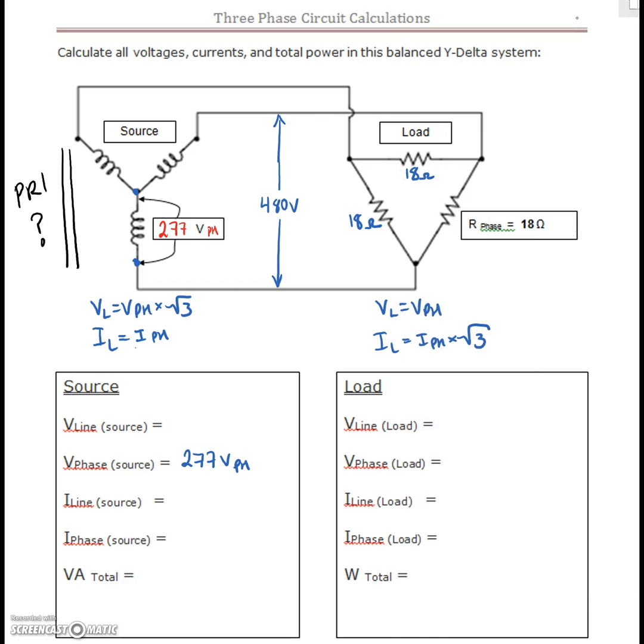Excellent, so our line voltage here is 480 volts on the line. We can clearly see that voltage goes across and is impressed right across our delta load there. That's 480 volts coming in, and we can see that the voltage here is the exact same as the voltage impressed right across our resistive load. That fits with our equations here, that our line voltage and our phase voltage are identical.